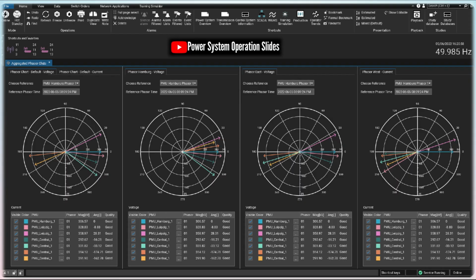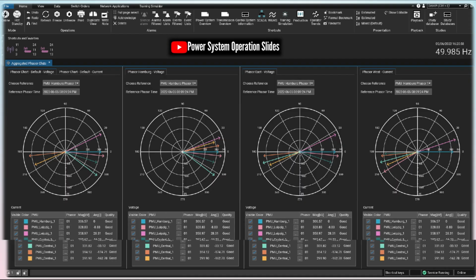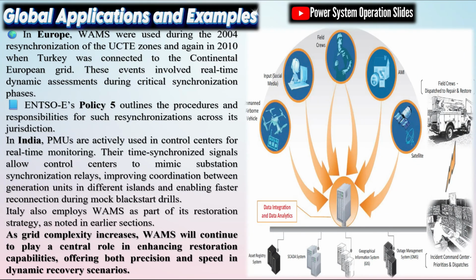During the restoration planning phase, synchrophasors combined with state estimation tools offer precise insights into the grid's condition, including island zones and available components. This data supports the development of effective restoration strategies. In the execution phase, synchrophasor inputs can be integrated into SCADA-based control modules to automate key actions such as load re-energization, island resynchronization, and generation ramp-up, ultimately reducing restoration time.